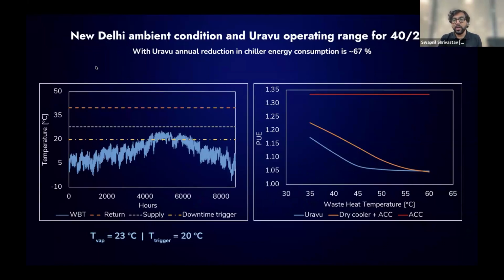There was one case study I wanted to share, for New Delhi as a location, which is very hot and dry and has very high PUE. If you just use air chillers, it will be almost 1.3, 1.4. And if you use a hybrid solution, even at 35, 40 degrees, it's still well above 1.2, 1.22. With our solution, we are able to reduce that PUE from 1.2 to 1.14. So you have a substantial saving in your overall energy reduction as well as your overall load.